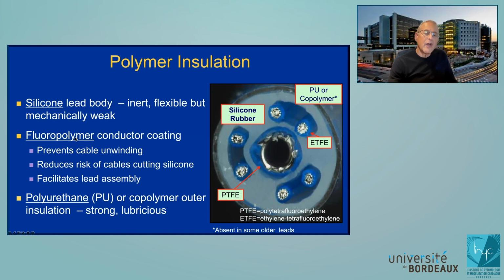The Teflon or Teflon-like polymers, for those of you who really want to know, ETFE and PTFE, have long names, and I'm not going to pronounce them. Basically, they keep the cables from unwinding. They keep the cables from cutting into the silicone. They make it easier to build these leads. And then finally, there's often some outer layer that's tougher than the silicone. Ideally, that should be both strong and slippery, because we don't like putting sticky plastic in veins. But we want it to be strong enough that we can't break or cut it, and even better if it were electrocautery resistant.